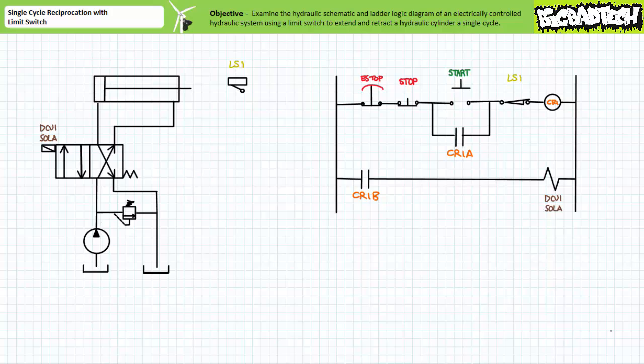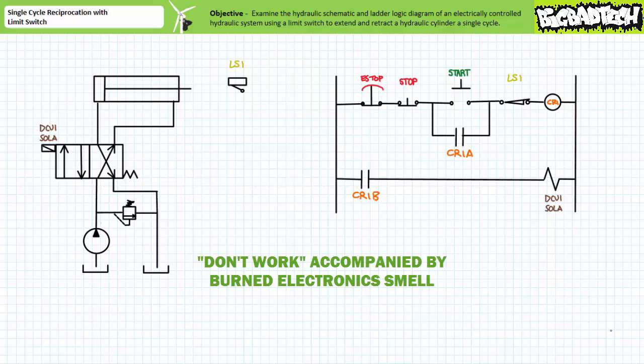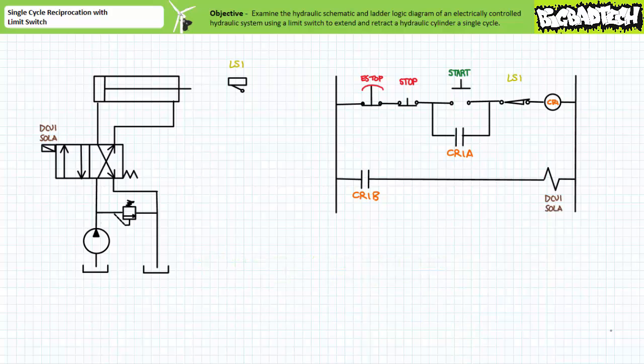Keeping systems clean is largely the purpose of low-level maintenance tasks — it is far easier to pinpoint a leak on a clean system than one with an accumulation of sawdust, grease, and filth. Most likely a fitting, hose, or seal is worn to the point of rupture. If this system was recently taken down for maintenance, research what actions were performed during the prior maintenance — perhaps the seal was improperly installed or overlooked during reassembly. Let's say you're called into another scenario and upon entering the room notice an ozone or burned electronic smell. The problem is quite obviously electrical in nature — some component has reached an early end of its life, most likely the power supply, relay coil, or solenoid.